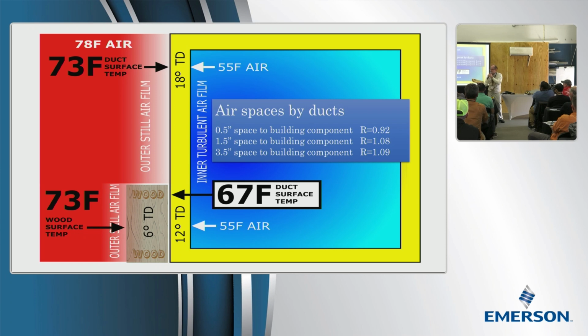You get a big bang just because it doesn't touch. So let's say a ½ inch, because at least we know our duct is going to be 73 degrees, not 67. We're in North Carolina, but we've had some houses with flex duct in the attics where it was put in new construction and was laying basically on the sheetrock. Then they came in and blew a lot of insulation on top of it. We've had some cases where we go over there and it's getting water spots on the ceiling, and that insulation is wet.